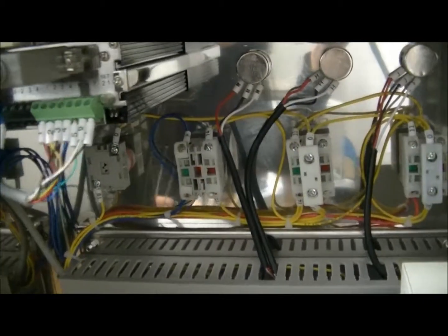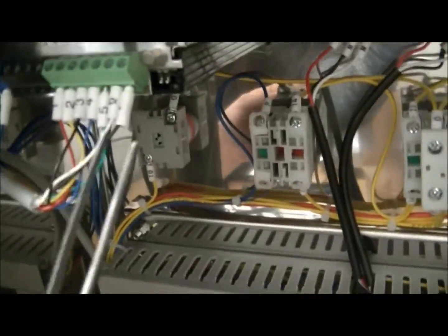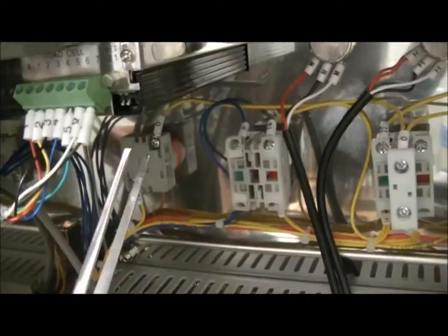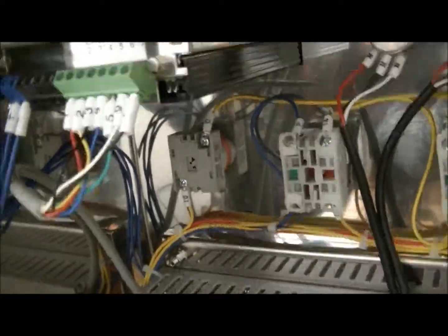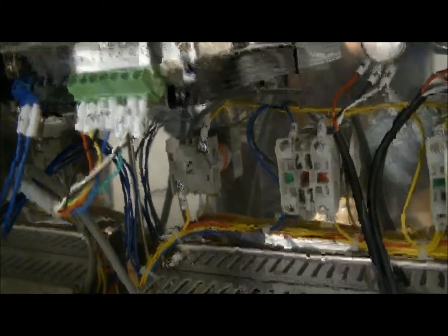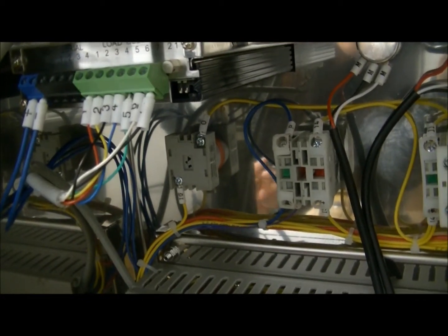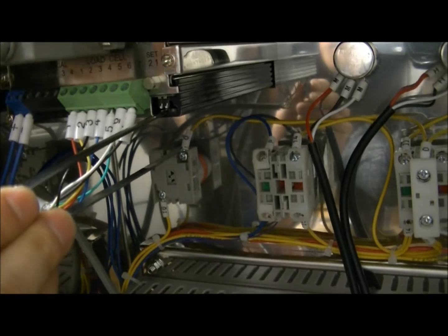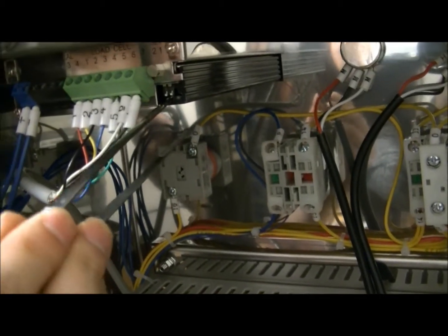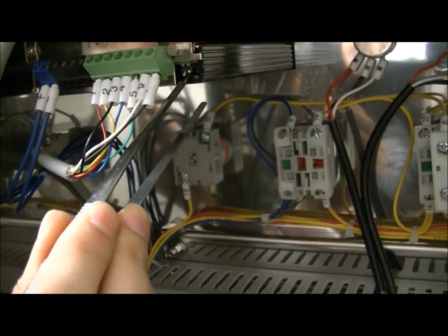So with the back of the machine open, we're going to locate at the top left of the machine, there's going to be a couple white switches right here. We are going to use a fine tip screwdriver or something else with a fine tip. In this case, I've got a pair of tweezers to flip the white switch on the right up. And once we do that, we'll be in calibration mode. Okay, now that we've put the machine into calibration mode by flipping the switch in the back, we can plug the machine back in and turn it on.